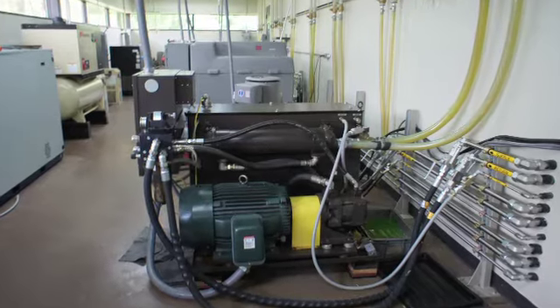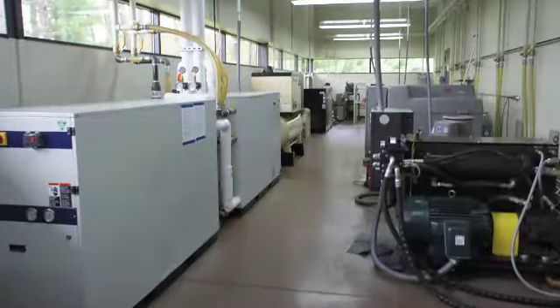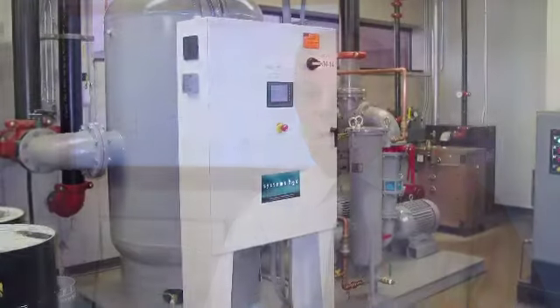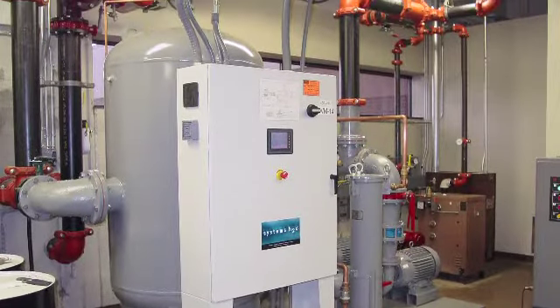We were able to reclaim about 775 million BTUs from the hydraulic system and from the chillers that was being wasted. The hydraulics and the chillers are there year-round. They use them in the wintertime. We grabbed that heat, and now, instead of sending it out to the cooling tower to just dissipate it, we actually took that heat and pumped it into the heat pump system, which is in of itself the air conditioning system running in reverse. So instead of cooling the air and dumping heat into the water, we're heating the air and basically cooling the water.